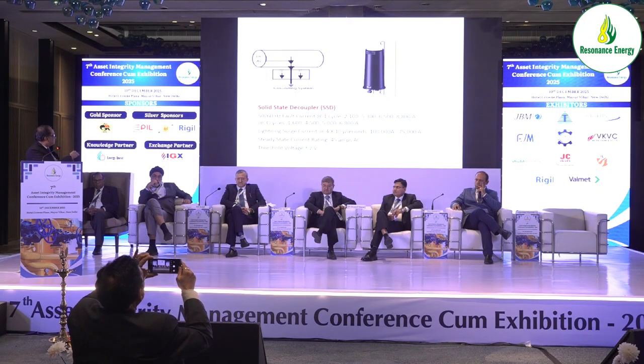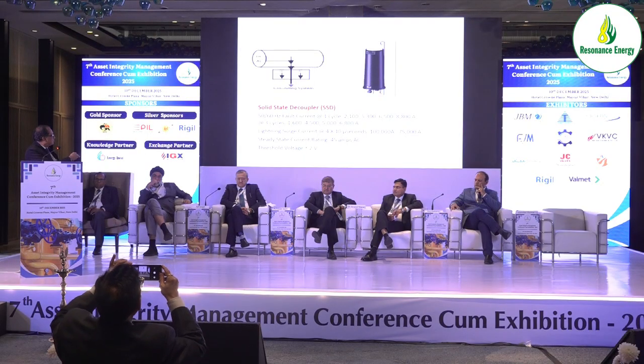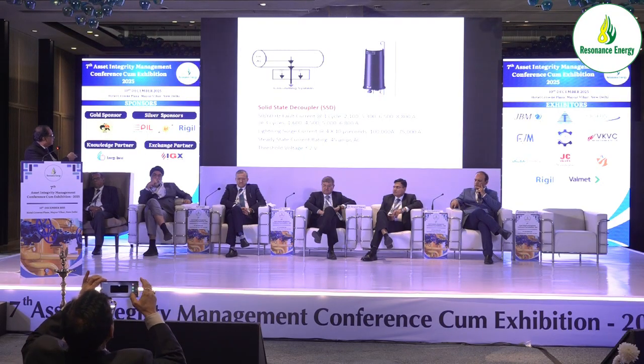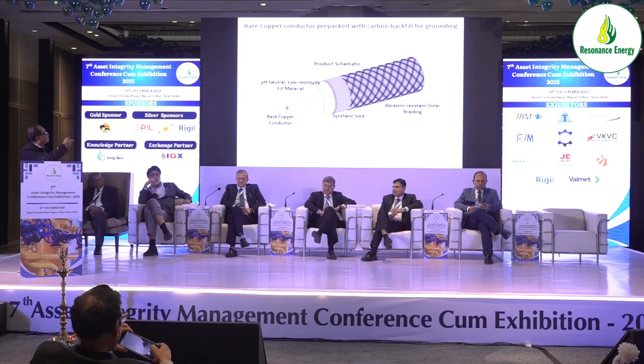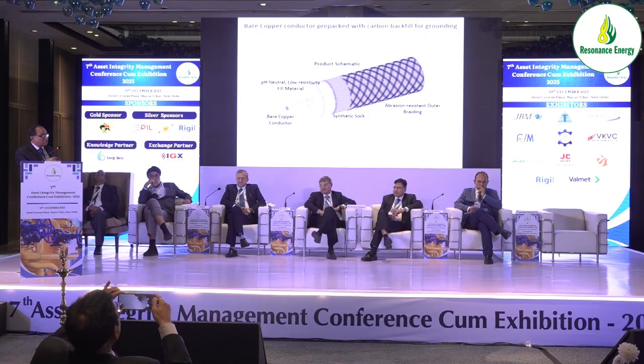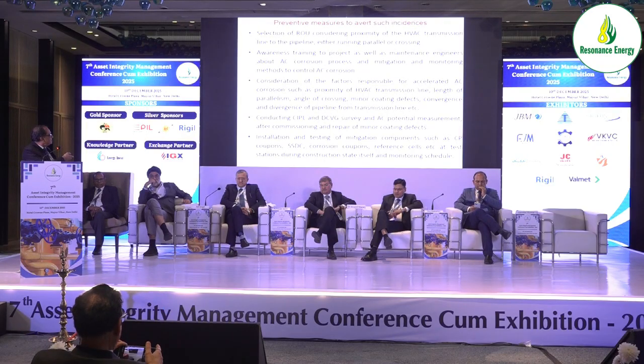See how much specification I have given: 3 cycles, 1600, 4500, 6800 ampere. You can increase it. You should know how much that fault current is, and accordingly you design. This is the bare copper conductor packed with carbon backfill for grounding. So don't rely on zinc anode. That is not for your grounding. So these are preventive measures. Same thing, you can read.